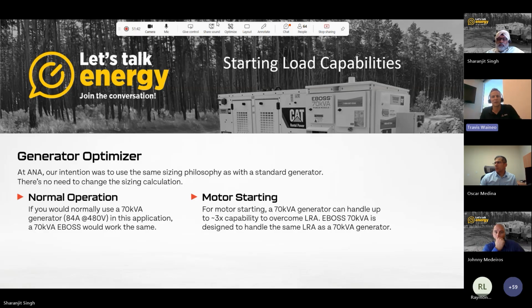And really what that allowed us to do: for a normal generator, the rule of thumb is you're designed to handle up to 3 times the generator nameplate for motor starting. So it's 100 milliseconds, a very short period of time. So a 70 kVA gen might be able to start a 210 kVA load, or about 150 kW load, for those 100 milliseconds just to get past the locked rotor amps. And so we did the same thing.